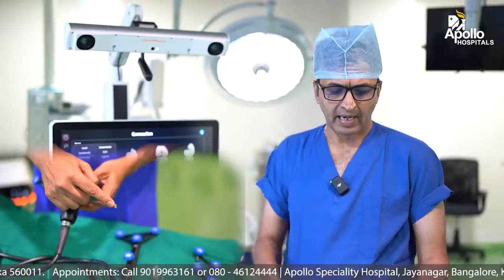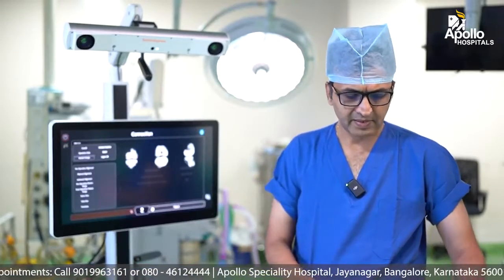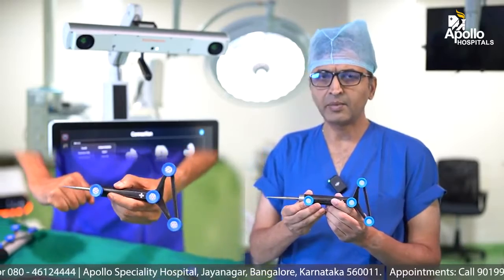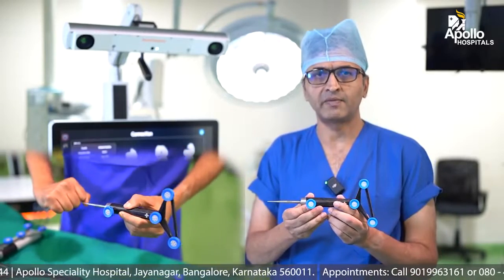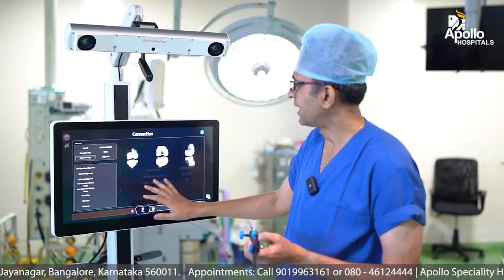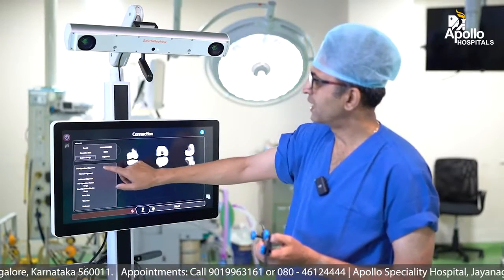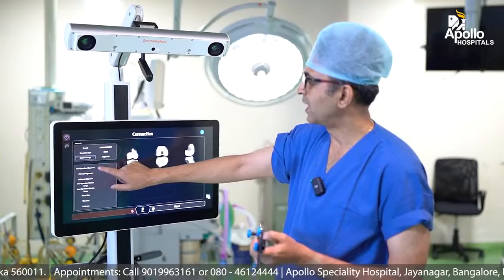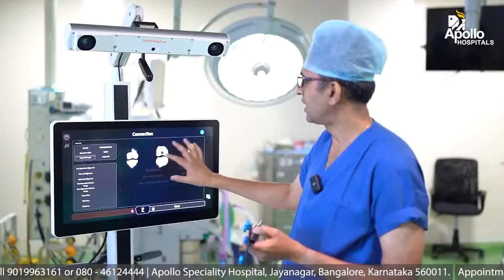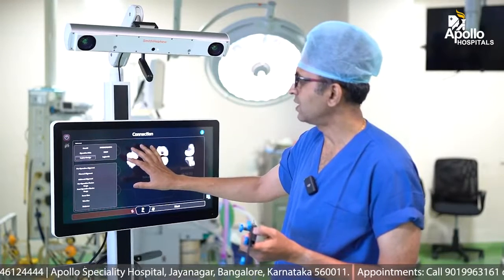This mills the bone, and the third thing is this probe — a handheld probe. We create a 3D model of the knee intraoperatively using this probe, as a result of which we get this data on the screen. We get something called a pre-operative alignment, and we can plan the cuts, the rotation, and other planning is done on the computer screen.